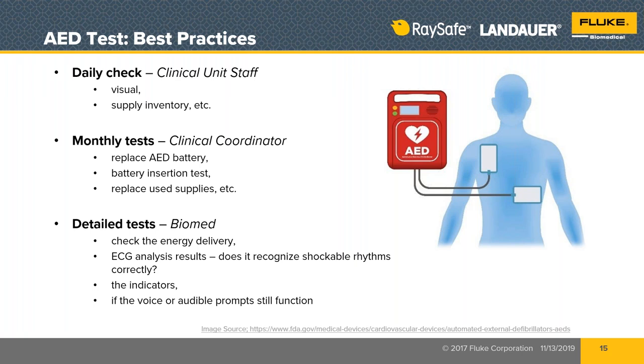Okay, so here's kind of the story about AED testing. Daily checks, monthly checks, those are things that are done by the clinical staff, not by the biomed. The detailed tests, which we will say are once or twice a year, are done by the biomed. These are checking output energy delivery, shock: what is a shockable rhythm? Is it properly identified? Things like that. Does it go into the CPR cycle properly? And does it leave the CPR cycle properly once the patient rhythm is converted to a more normal rhythm? Voice prompts and so forth like that, alarms, all of that need to be tested by the biomed.